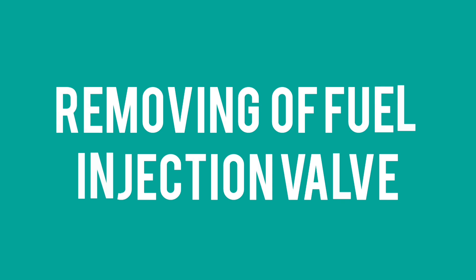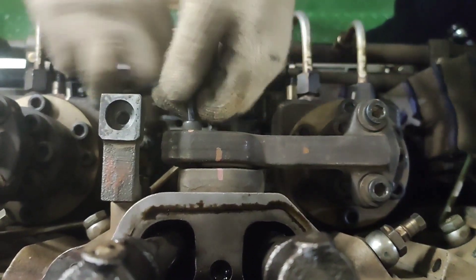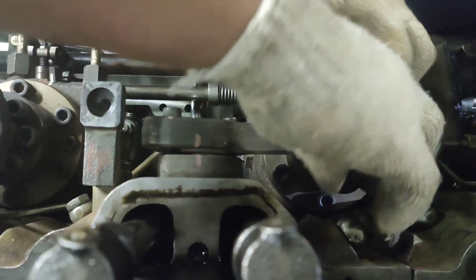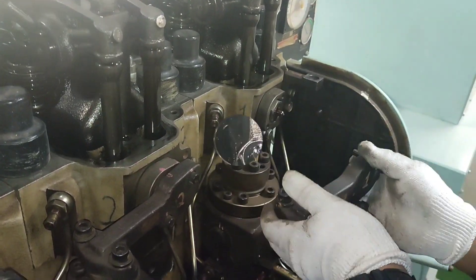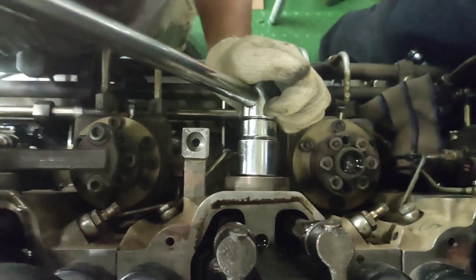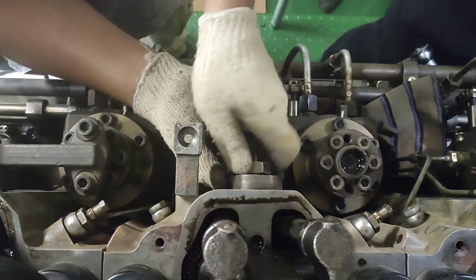Removing the fuel injection valve: Remove the clamping bolts of the injection pipe joints on the fuel injection pump side with a hexagon wrench. Remove the injection pipe joint. Remove the injection valve tightening nut. Loosen the injection pipe cap nut and remove it together with the injection pipe.